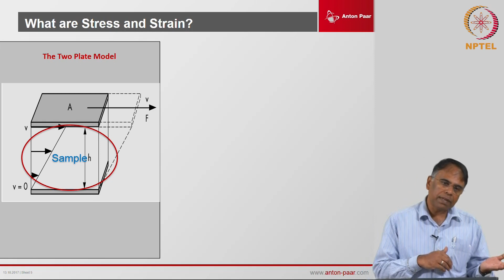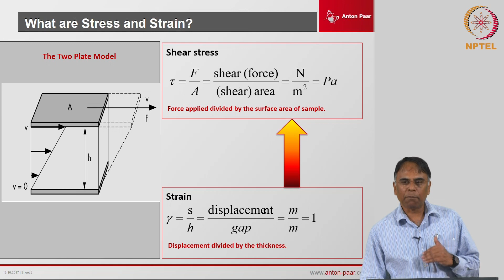When I move the upper plate with a certain displacement or a certain speed, I require a certain amount of torque to get that defined displacement or speed. That measured torque divided by the surface area gives you the stress value. So the torque divided by the surface area is your stress, and velocity by gap and displacement by gap give you the shear rate and the shear strain respectively. This is how the measurements take place on a rheometer. You can apply either the shear stress and measure the shear strain, or apply the shear strain and measure the shear stress.